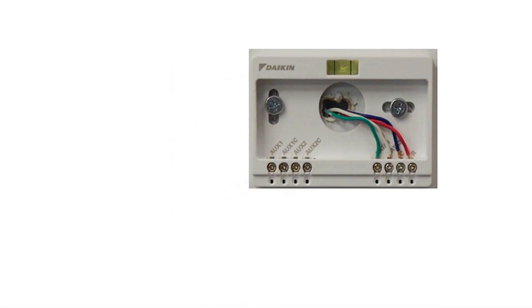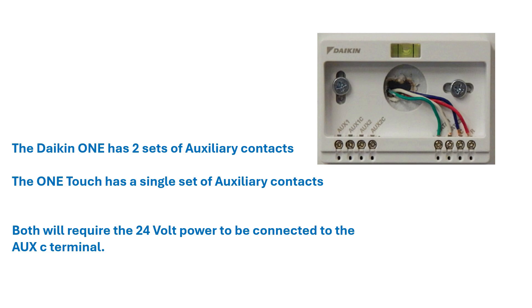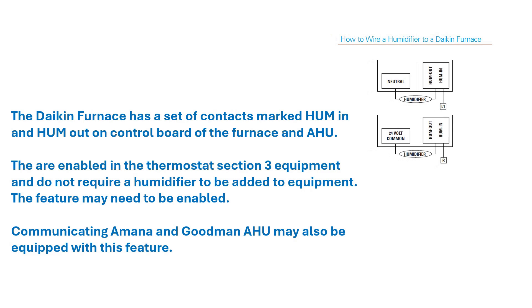Here's a quick look at the sub base of the Daikin One. The Daikin One has two sets of auxiliary contacts, where the One Touch has a single set of auxiliary contacts. Both require power on the C terminal — the 24 volts will go to the C terminal before leaving on the auxiliary terminal. The Daikin furnace itself has a humidifier hum-in/hum-out contact along with the air handler, and you may see a setup in Section 3.